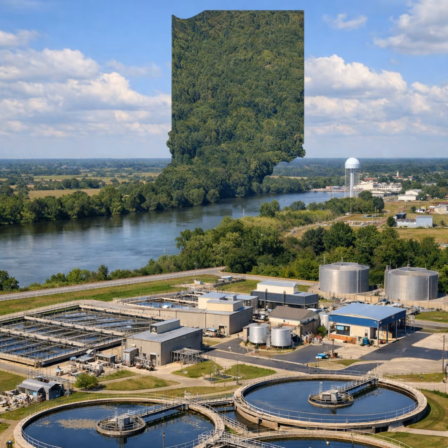And the activated sludge process is also described as a mixed blend of microorganisms, 95% of which are a variety of mostly aerobic species of bacteria. So that's a key for what activated sludge is. 95% of those microorganisms are mostly aerobic species of bacteria. So that's something that's important to know.